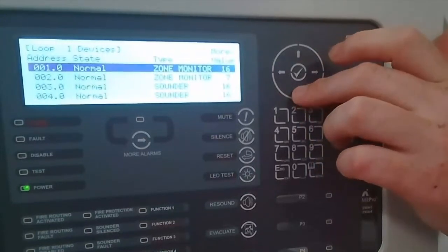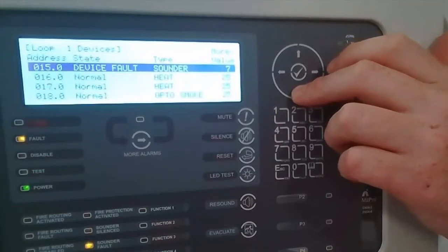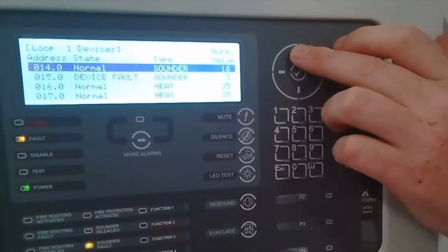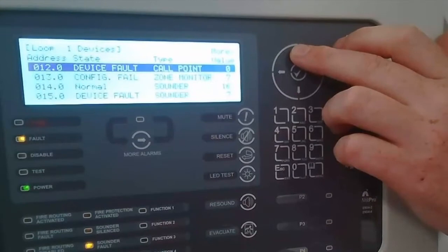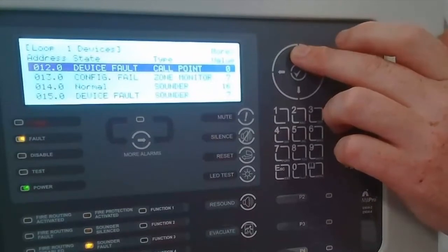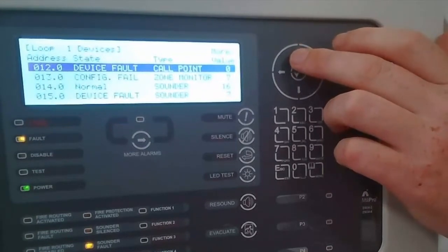If I scroll down, they're all reporting as normal. But there are a couple of device faults — for example, that may be a battery level or a tamper message. Some other devices have a device fault or configuration fail. So without the panel knowing that they are the AMS Fire Cell type devices, they can't report the correct device states.